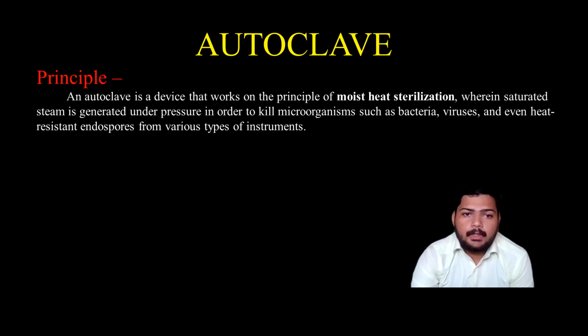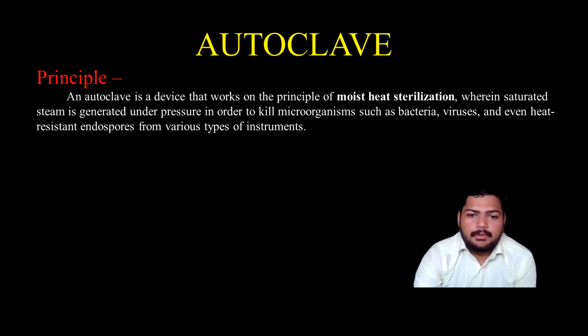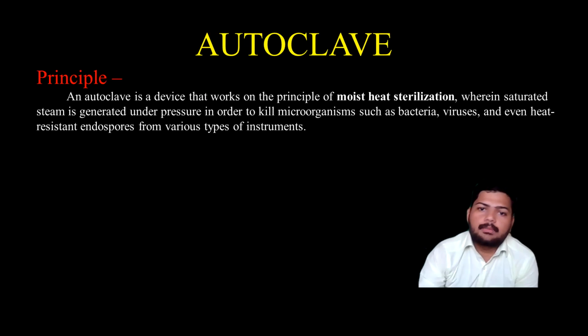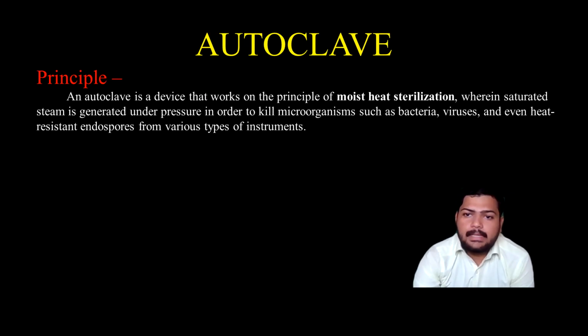First one is the autoclave. Autoclave means automatically locking, that is what the name really means. It has a steel container in which the temperature and pressure are increased to kill microorganisms by using steam. The principle behind it is that an autoclave is a device that works on moist heat sterilization, due to which we use the steam. Saturated steam is generated under pressure in order to kill microorganisms such as bacteria, viruses, and even heat resistant endospores from various types of instruments.